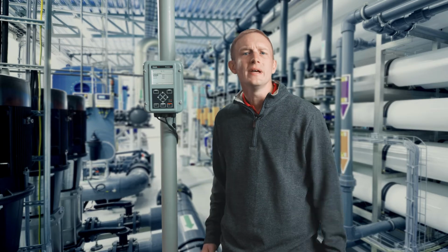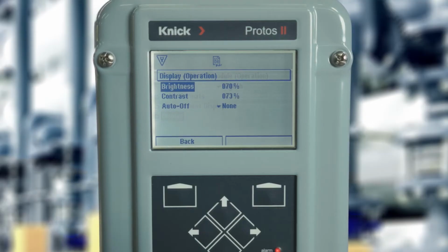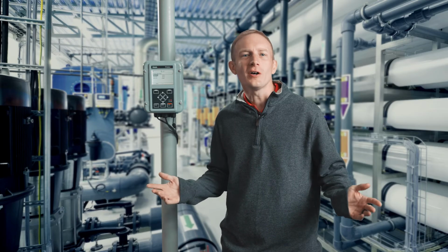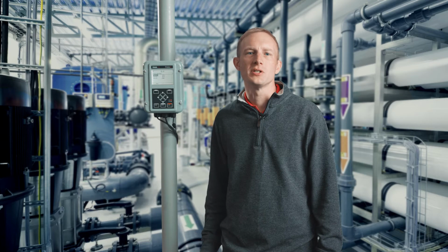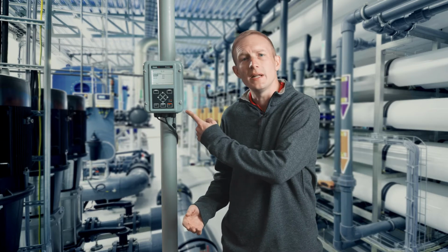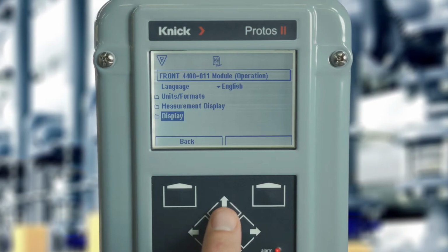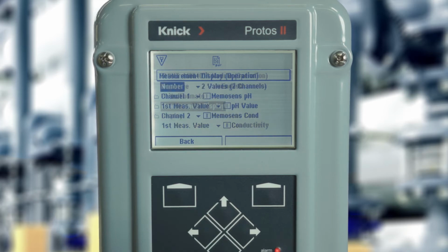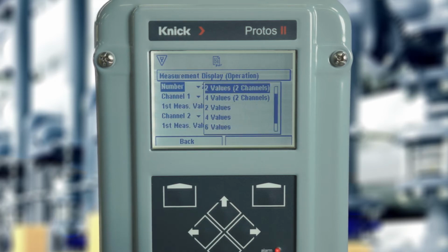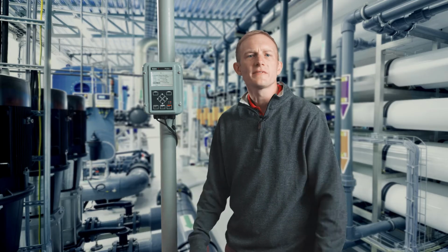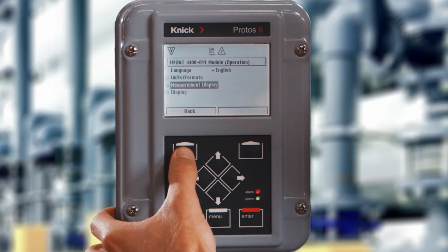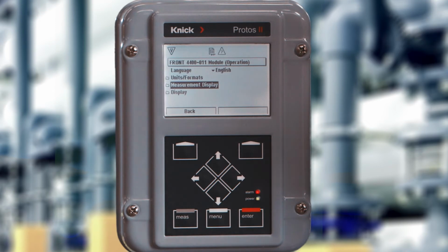In this menu, it is possible to adjust the brightness and contrast of the screen and to turn on the auto off feature. Please note, if you've also purchased the measurement recorder option, it can be configured within this menu. We will select our desired units of measurement as well as our displayed values on the main screen, which will be 2 values for 2 channels. Pressing the left square button will take us back to the main parameter setting menu.